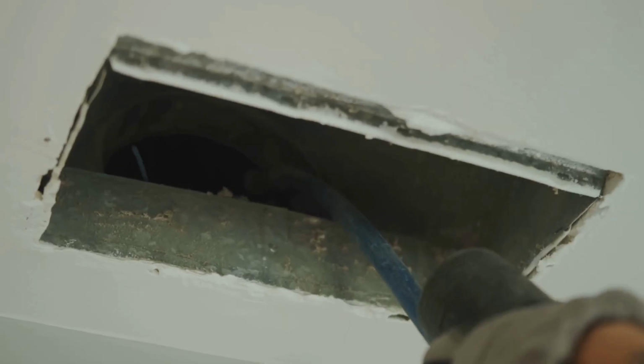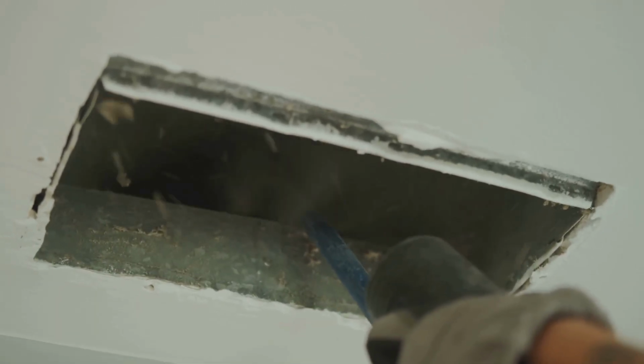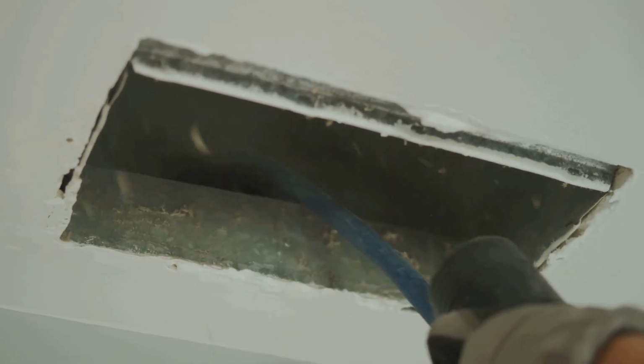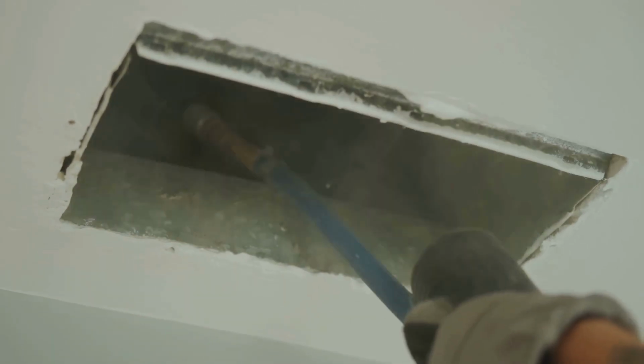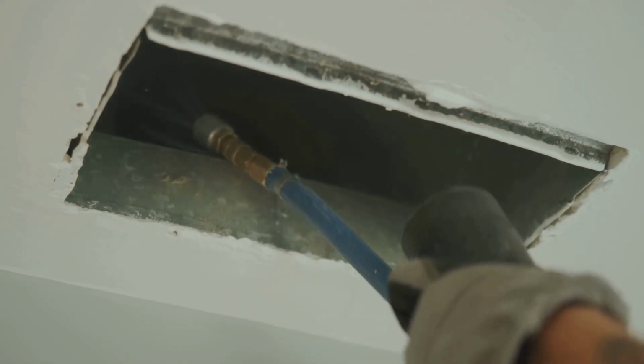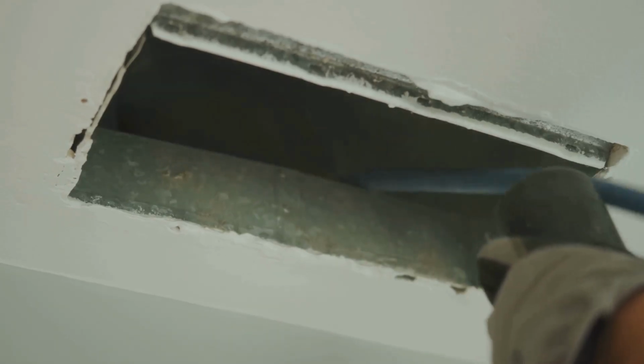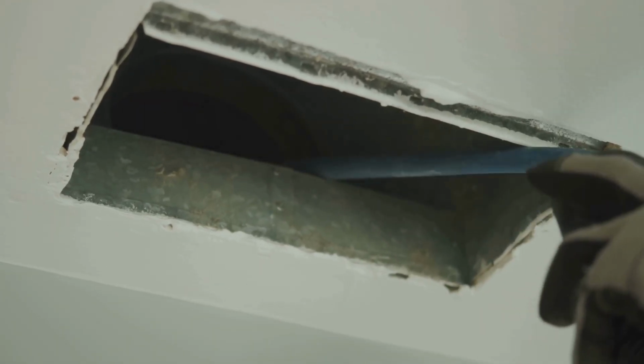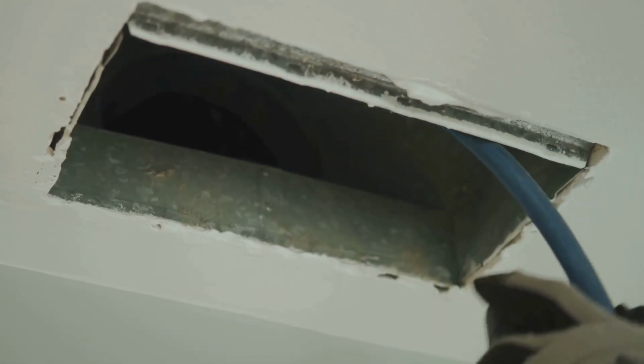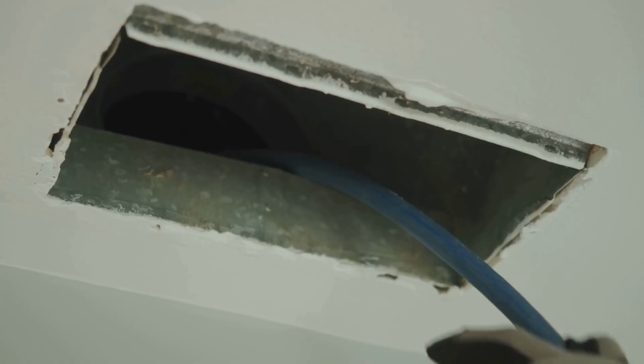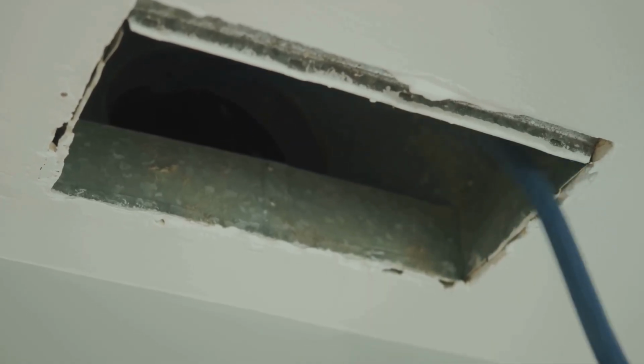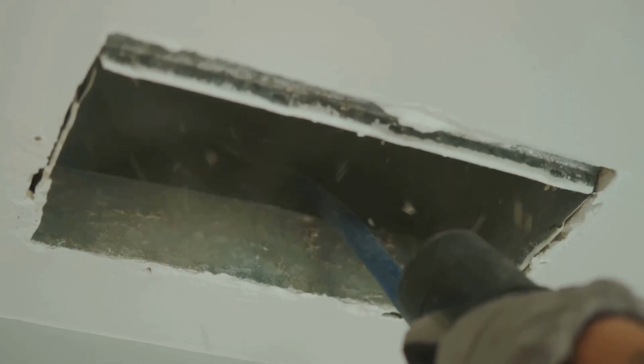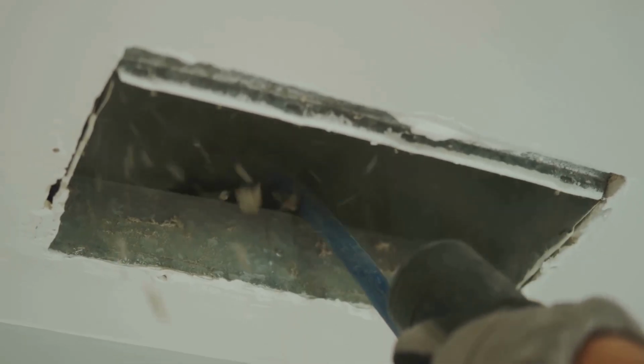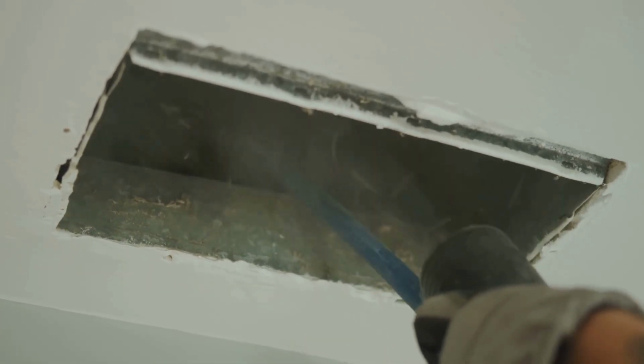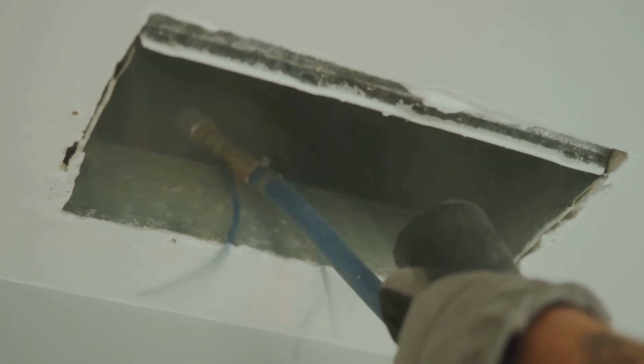The common temptation is to grab duct tape, but despite the name, it's the wrong tool. Standard duct tape dries out and peels away. The professional fix is mastic sealant. It's a gooey paint-on substance that creates a permanent flexible seal. For larger gaps, use it with special fiberglass mesh tape. It's a messy job, but the payoff is huge. Sealing your ducts can improve your HVAC system's efficiency by as much as 20%.